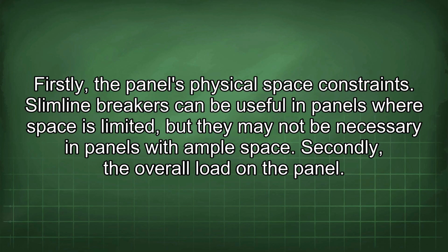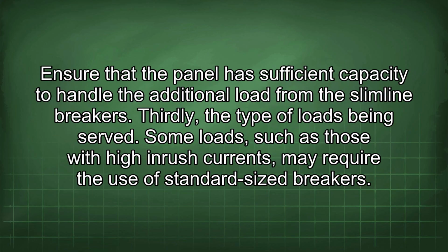Firstly, the panel's physical space constraints. Slimline breakers can be useful in panels where space is limited, but they may not be necessary in panels with ample space. Secondly, the overall load in the panel. Ensure that the panel has sufficient capacity to handle the additional load from the slimline breakers. Thirdly, the type of loads being served. Some loads, such as those with high inrush currents, may require the use of standard size breakers.